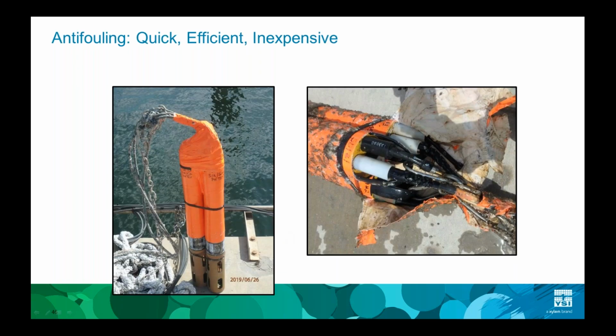This particular photo is of a triple sonde deployment at our Florida test site. I simply wrapped the top end of the sondes with duct tape before deployment, and then post-deployment carefully cut the tape off to reveal nearly spotless top ends of the sondes. With no light getting into this area during deployment, we did not see the amount of growth that we would otherwise experience. This simple, inexpensive step turns what would have been 90 minutes of scraping and cleaning into about 5 minutes of work.